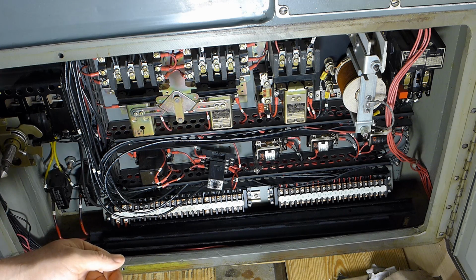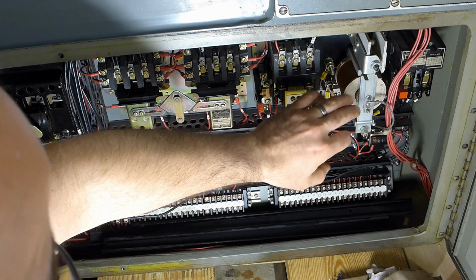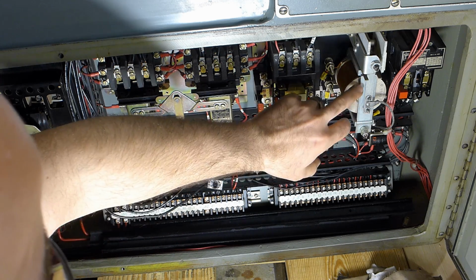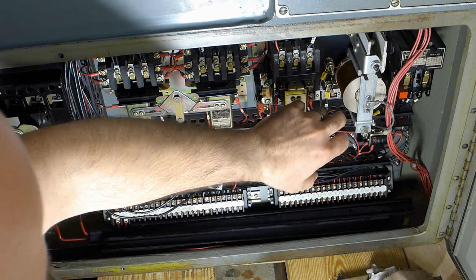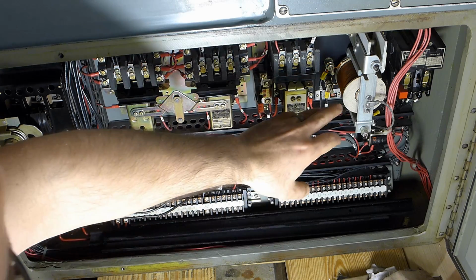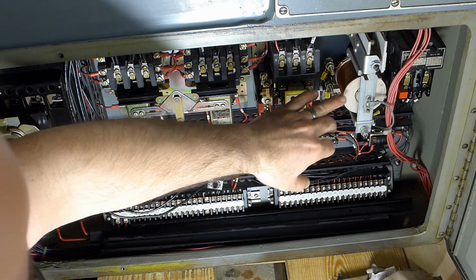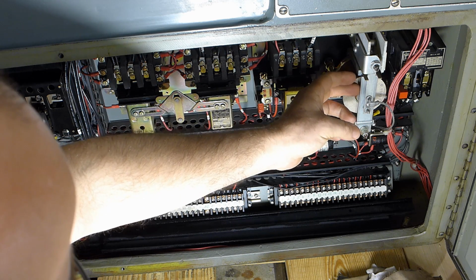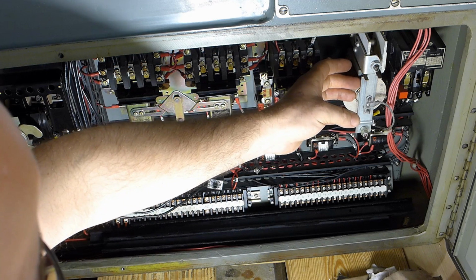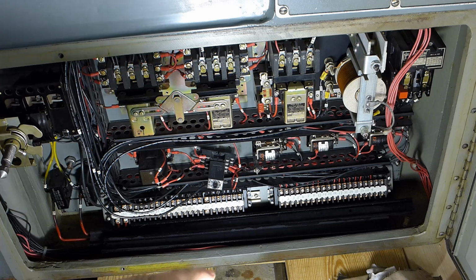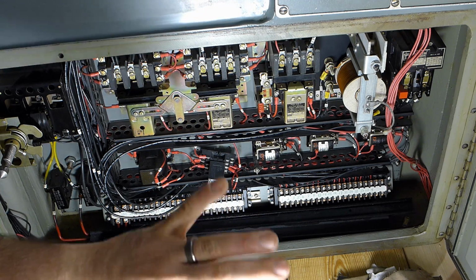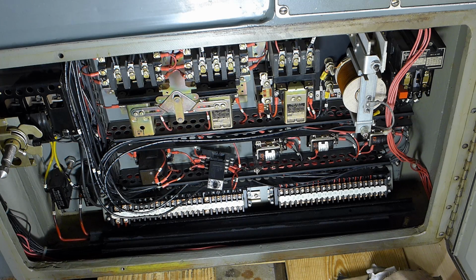There were a few terminals that were loose. There was a little bit of, not corrosion, but arc damage. This right here is what essentially, if you want to slow down quickly, it's called a quick slowdown. But the change in armature current causes a field to develop here, which engages this, and this causes the armature leads to the motor to get bridged, where the EMF slows down the motor quickly. Dynamic braking. It's basically just like in your hybrid car, although that's regenerative braking, but it's a type of dynamic braking, so that you're using the electric motor's field as an internal brake, so a non-physical brake.